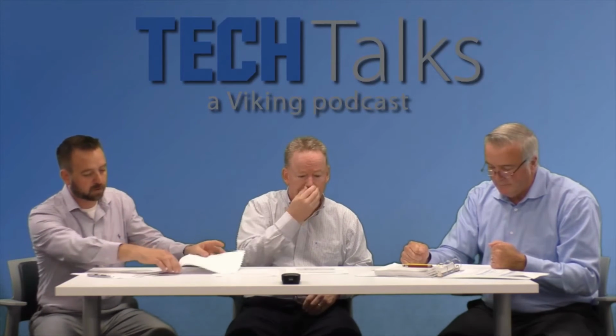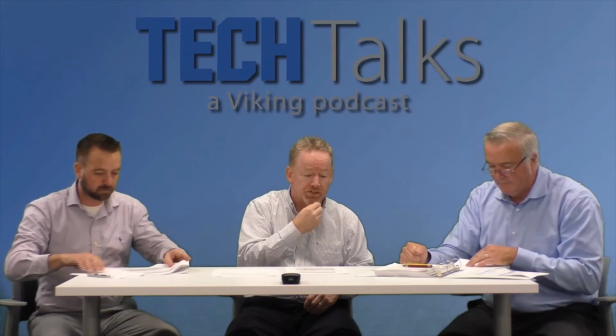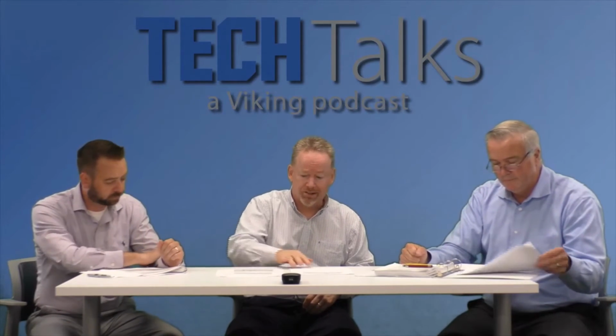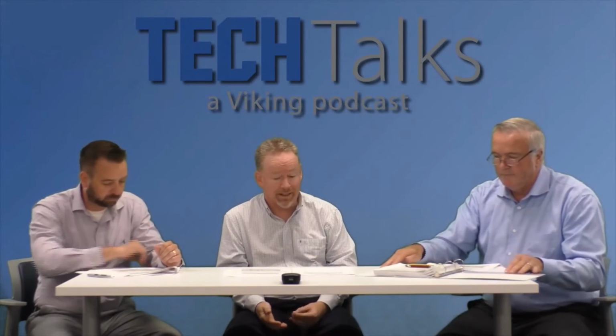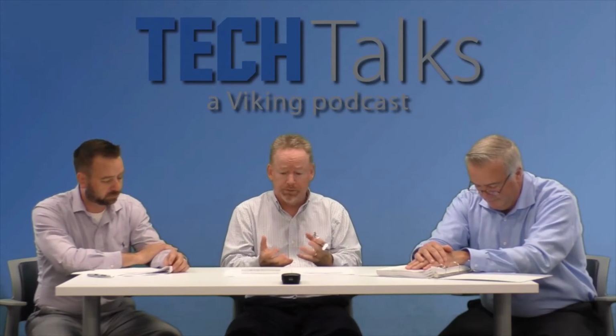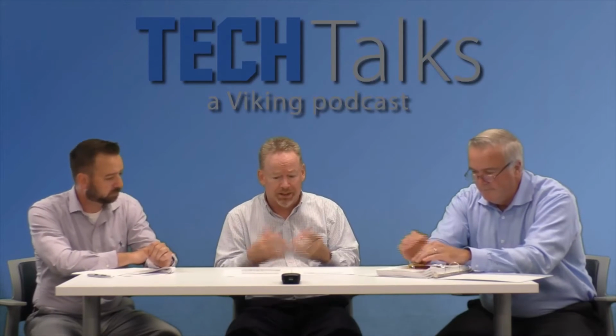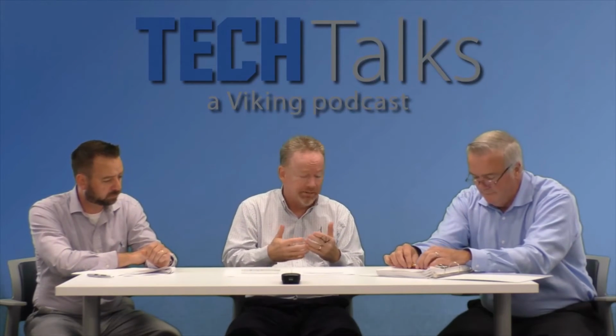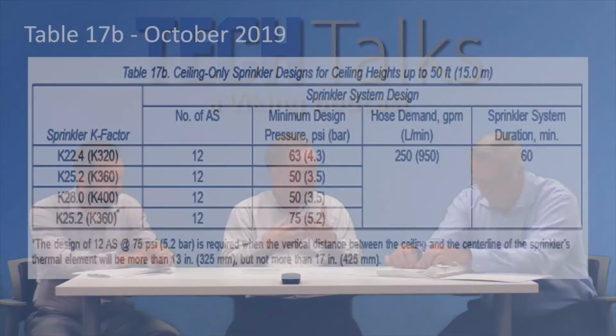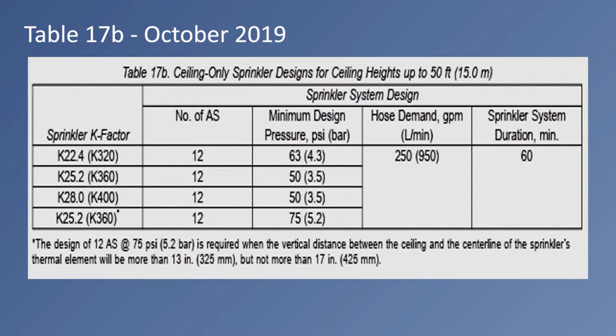Okay, so let's explore a little bit deeper the January and July revisions to 17B, because it wasn't but a year ago, actually October of 2019, that Table 17B was a very straightforward, fairly simple table that basically set up pressures and the number of sprinklers, 12, and it had all of the necessary guidance that you needed.